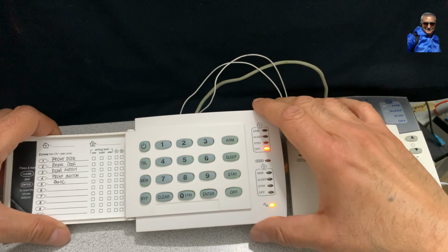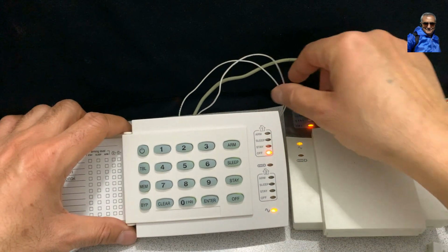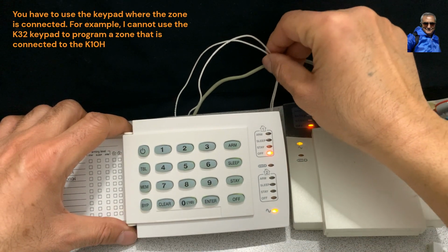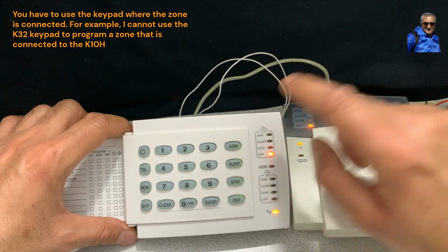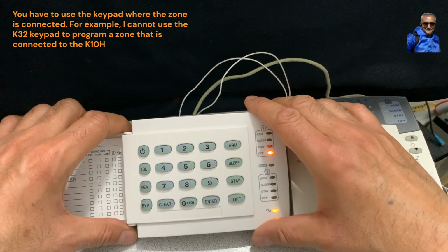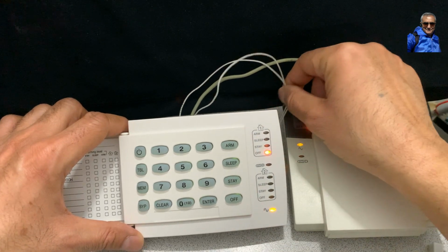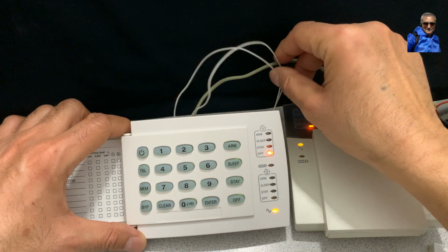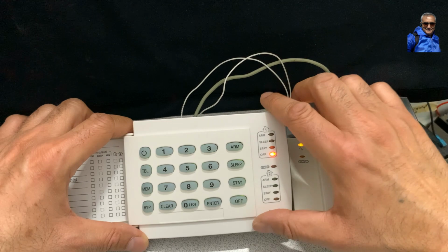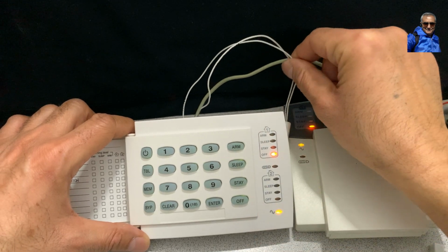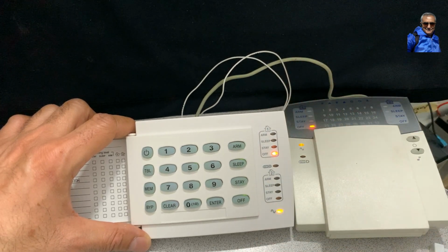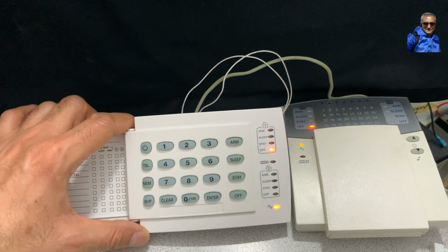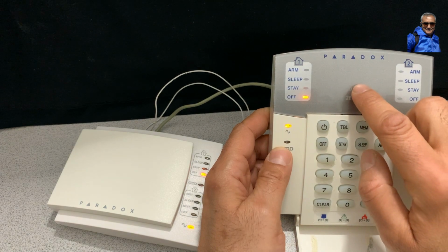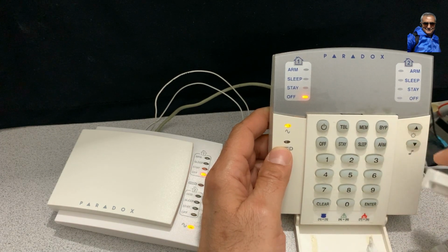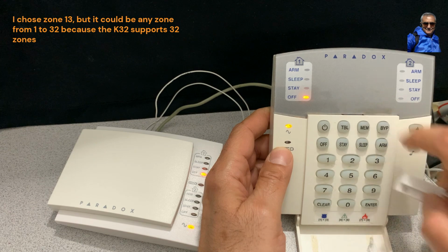Now, to program the keypad zone on a keypad, you have to use that keypad where the zone is connected. In my example, I will program the door contact on the K10H keypad to be my Zone 1. This means that Zone 1 will be a keypad zone rather than a panel zone. I will show you what this means later in the video. On the K32 keypad, I choose to have my keypad zone to be on Zone 13. Could be any zone you choose.